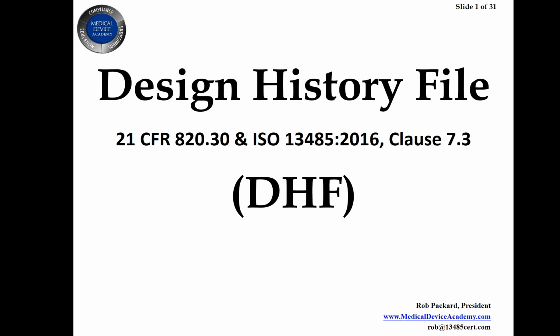And then recently, ISO 13485:2016 was updated. March 1st, they released the final version of the standard. And they've modified clause 7.3, so now there's 7.3.10 that specifically adds the requirement for a medical device file or medical device development file. And that's intended to not only meet the requirements for a DHF to satisfy the FDA, but it's also supposed to refer to the requirement for maintaining a technical file and design dossier for both Europe and Canada and other countries as well that require it for any medical devices.